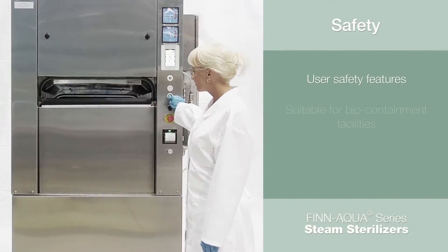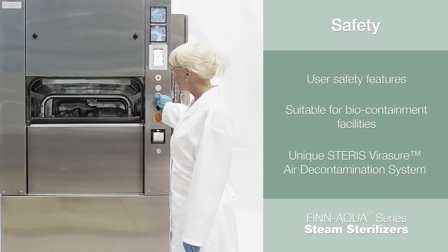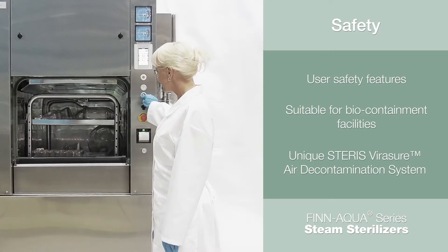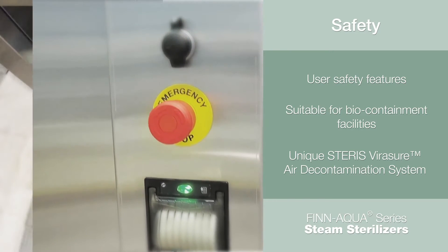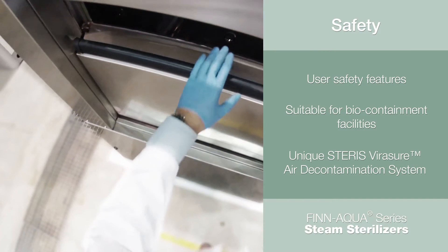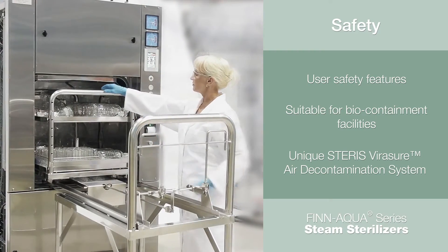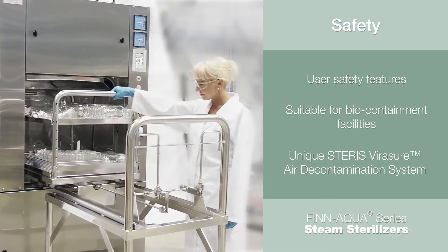At STERIS, safety is of paramount importance. The FINN-AQUA Series sterilizers are equipped with a number of standard safety features: emergency stop buttons, access codes, door sensing devices, and sensors that prevent steam flow while the door is open, as well as prohibit the door from opening while the chamber is pressurized — all present to prevent injuries and increase overall safety.